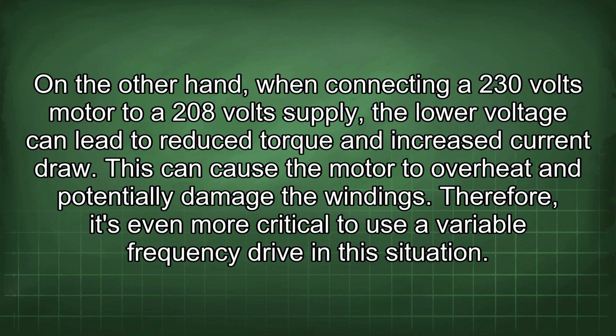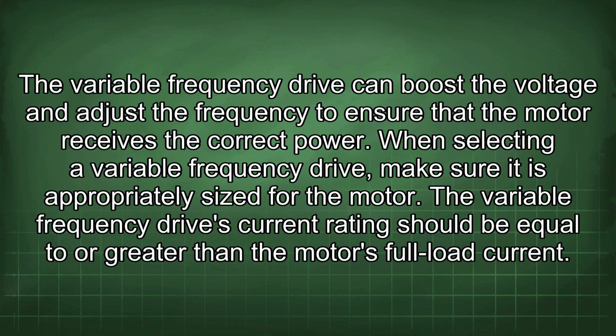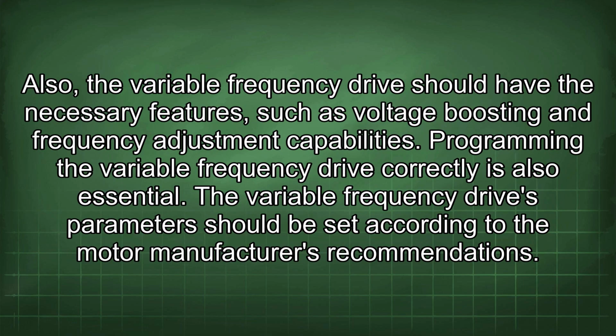Therefore, it's even more critical to use a variable frequency drive in this situation. The variable frequency drive can boost the voltage and adjust the frequency to ensure that the motor receives the correct power. When selecting a variable frequency drive, make sure it is appropriately sized for the motor. The variable frequency drive's current rating should be equal to or greater than the motor's full load current. Also, the variable frequency drive should have the necessary features such as voltage boosting and frequency adjustment capabilities.